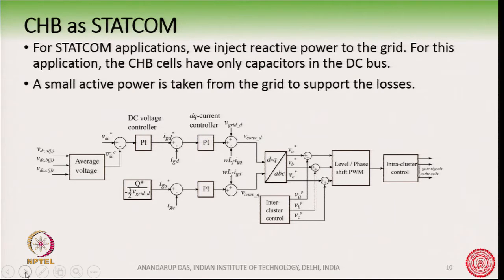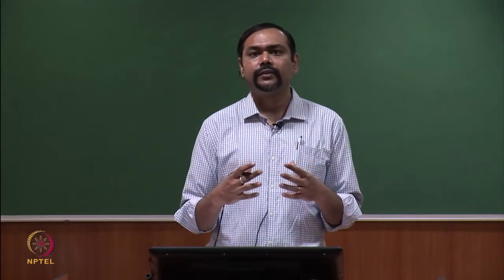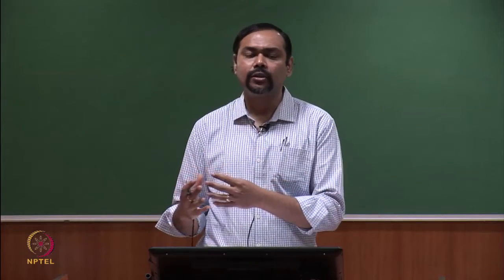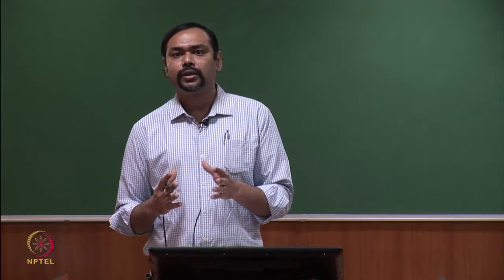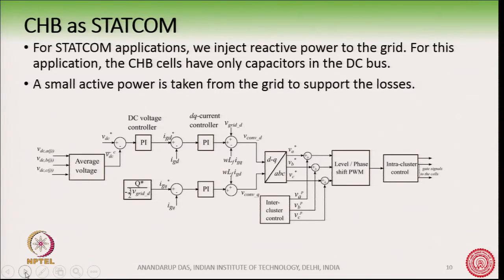Now, the CHB for a STATCOM application. Now, you know what a STATCOM is? A STATCOM is a static compensator which injects reactive power to the grid. If the grid wants reactive power so as to support some load, so as to make unity power factor or to subside some of the disturbances, then it asks for some reactive power from the grid connected converter, and STATCOM is such an equipment.